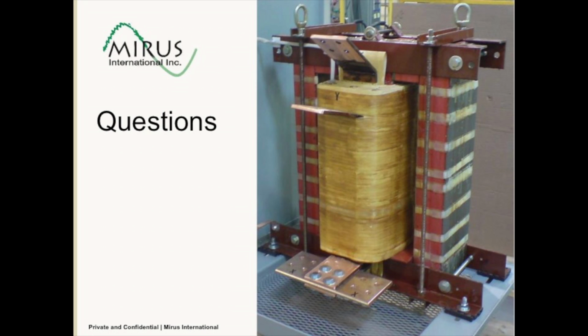Sometimes when you're just paralleling a generator with the utility, you have a single generator, you're paralleling it with the utility transformer. It's not combined generator systems. But there are circulating currents between the generator and the utility transformer, and the utility won't allow access to their neutral. Then really the only option you have is an NGI or an NGR. And again, we would recommend the NGI because of the triple frequency effect.